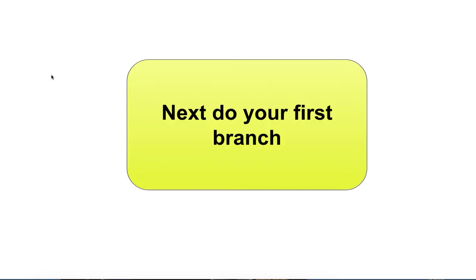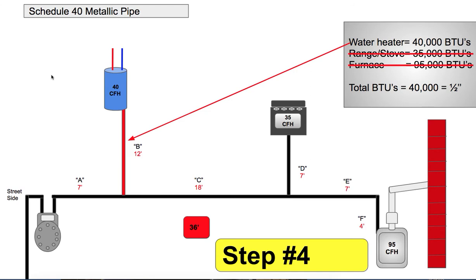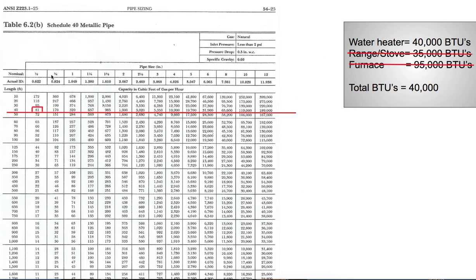Now you can do your first branch. The first branch serves the water heater at 40,000 BTUs. In the 40-foot column, the lowest we can go is half inch, which gives us an allowance of 81,000 BTUs — that's more than enough for 40,000.